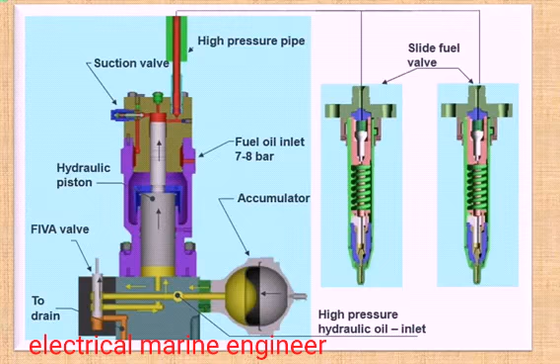Next is the electronic fuel injection valve, named the ELFI or FIVA valve. It is a proportional control valve, a solenoid valve, which acts as a pilot valve for the main spool valve. This is controlled by the PCB, which is a computer processor, which will activate the voice coil drive, which will move the spool of the pilot valve, and the end of the pilot valve has a self-centering spring, which fails safe.